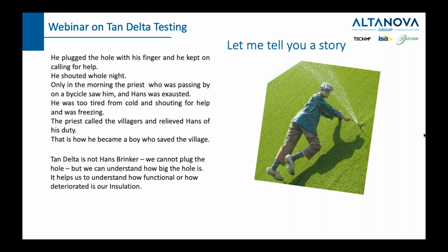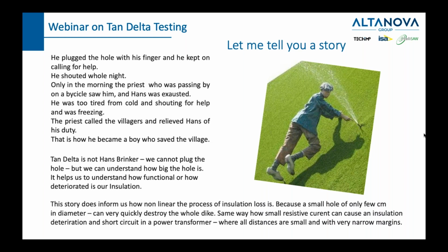We cannot plug the hole, but we can understand how big the hole is. We can understand how much resistive current is flowing in our insulation and heating it up. It helps us to understand how functional or how deteriorated our insulation is. So this story does inform us how nonlinear the process of insulation loss is, because a small hole of only a few centimeters in diameter can very quickly destroy the whole dike.